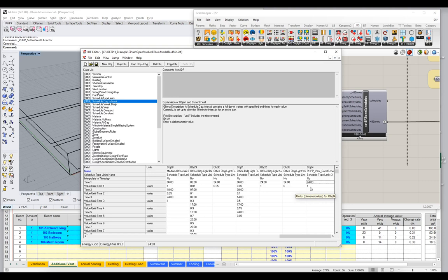Now this is not as realistic, as accurate I guess, as the detailed, variable, out-of-the-box schedules that you can find in Energy Plus. The reality is that the ventilation flow rates are going to go up and down over the course of a day. And certainly if this was a non-residential application, this would not be very accurate at all. But so that we can get good alignment between the Energy Plus and the PHPP, if that's what we want, and we often do, this is the way that we can override the Energy Plus out-of-the-box operation and make it work more like the PHPP.